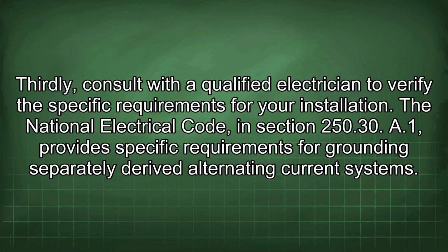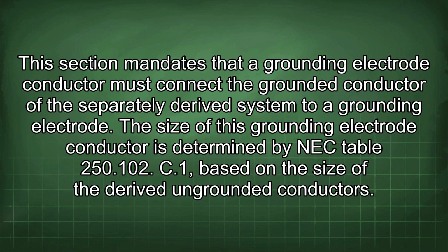The National Electrical Code, in section 250.30(A)(1), provides specific requirements for grounding separately derived alternating current systems. This section mandates that a grounding electrode conductor must connect the grounded conductor of the separately derived system to a grounding electrode. The size of this grounding electrode conductor is determined by NEC Table 250.102(C)(1), based on the size of the derived ungrounded conductors.